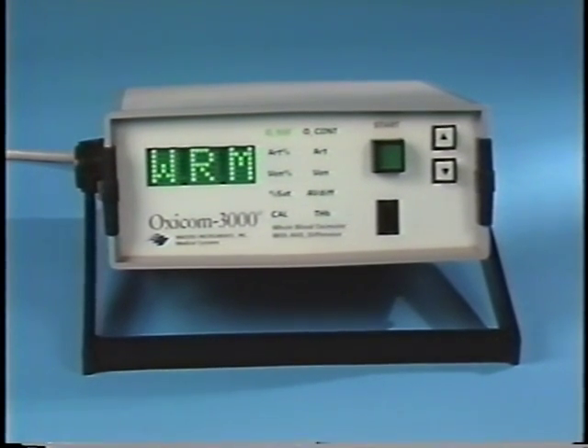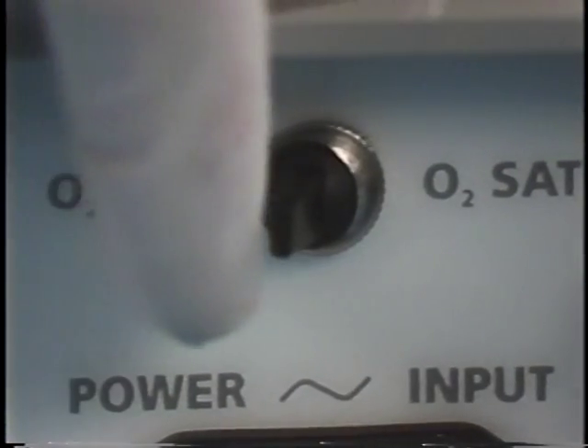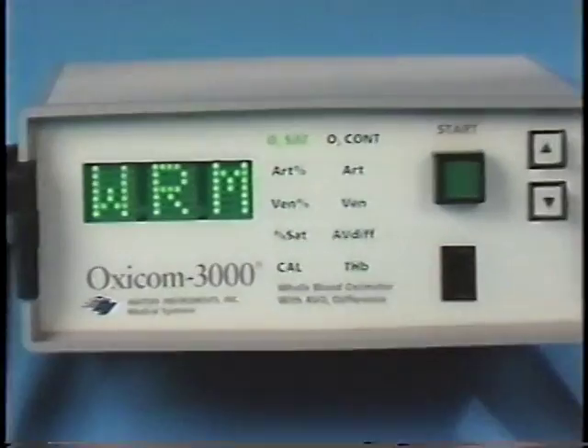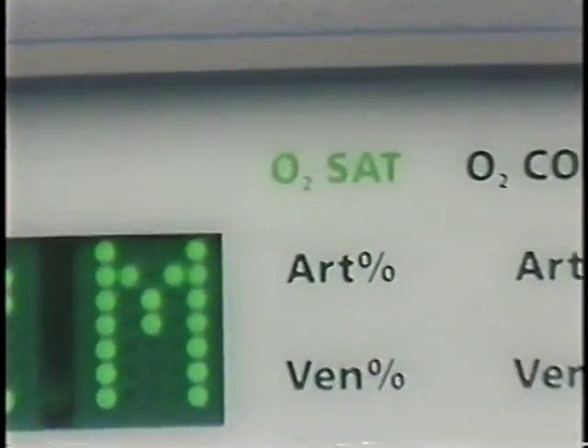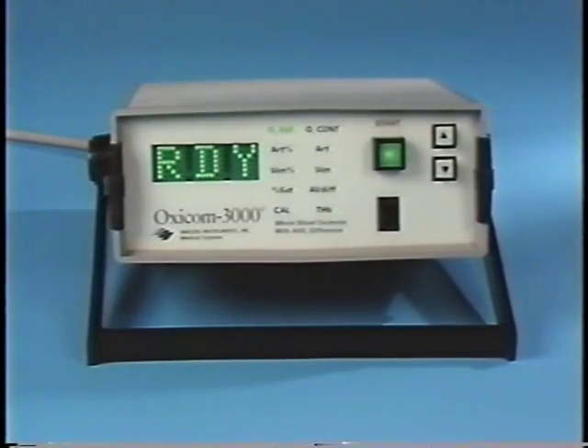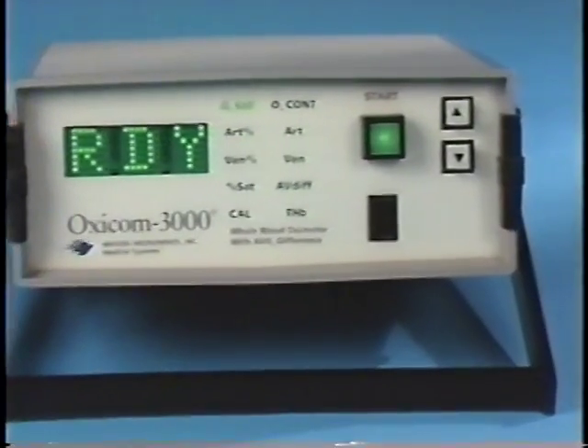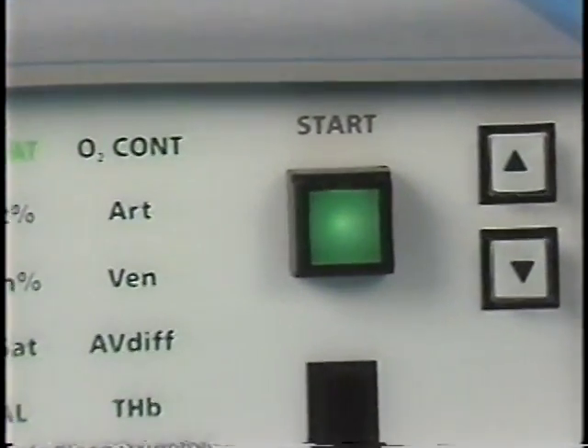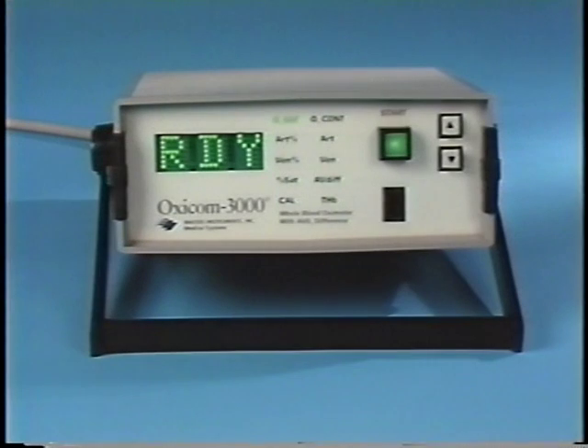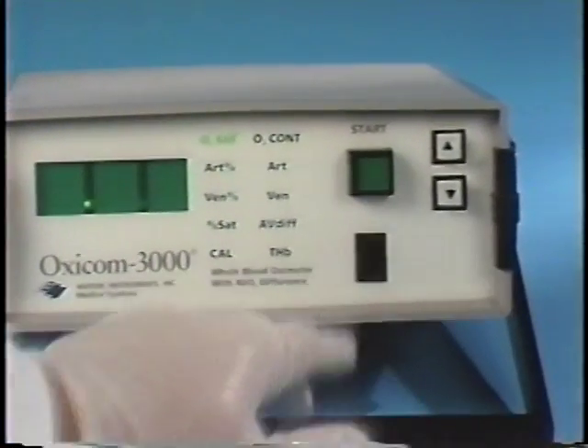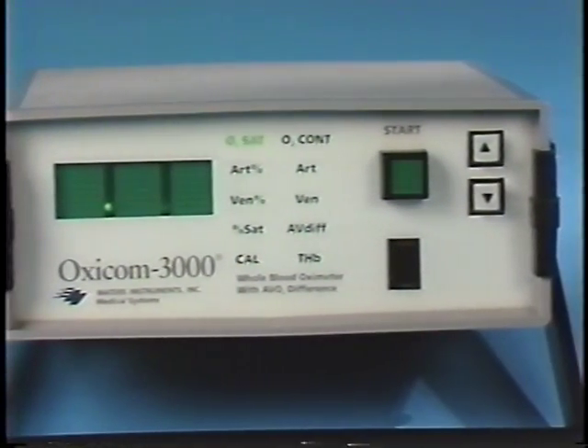To measure oxygen saturations, place the mode switch, also located on the back panel, in the SAT mode. Note that O2 SAT is now lit on the mode display. After the warm-up period has elapsed, the measurement display will automatically show RDY for ready, and the green start button will light. The Oxicom 3000 is now ready to measure samples. Press the green start button. Notice that the start button goes off and the display clears.